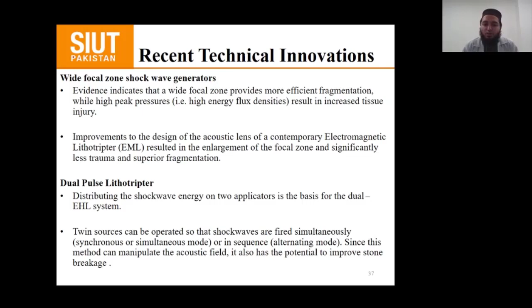Dual pulse lithotripter. Distributing the shock wave energy onto two applicators is the basis for the dual EHL system. Twin sources can be operated so that the shock waves are fired simultaneously, in synchronous or simultaneous mode, or in sequence, in alternating mode. Since this method can manipulate the acoustic field, it also has the potential to improve stone breakage.